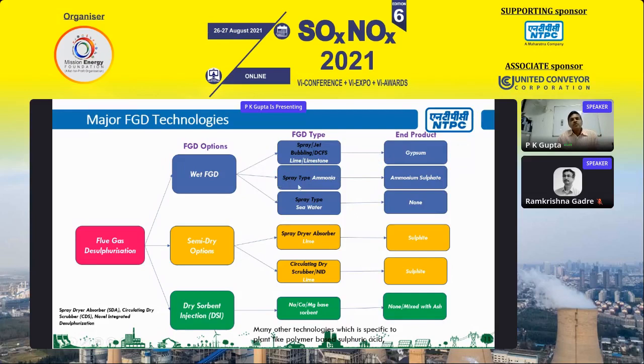The second technology is ammonia-based, which is also spray type, but here the reagent is different. Instead of limestone, it uses ammonia, and the byproduct is ammonium sulfate. Then there's seawater FGD, also spray type, with no byproduct. This covers wet FGD.